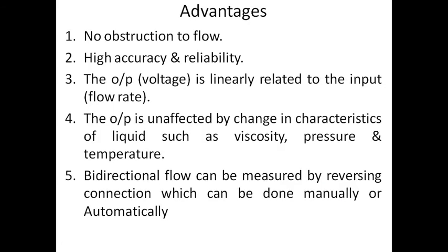Then advantages: there is no obstruction to flow, it has high accuracy and reliability, and the output voltage is linearly related to the input flow rate. The output is unaffected by changes in characteristics of liquids such as viscosity, pressure and temperature. Bidirectional flow can be measured by reversing the connection, which can be done manually or automatically.